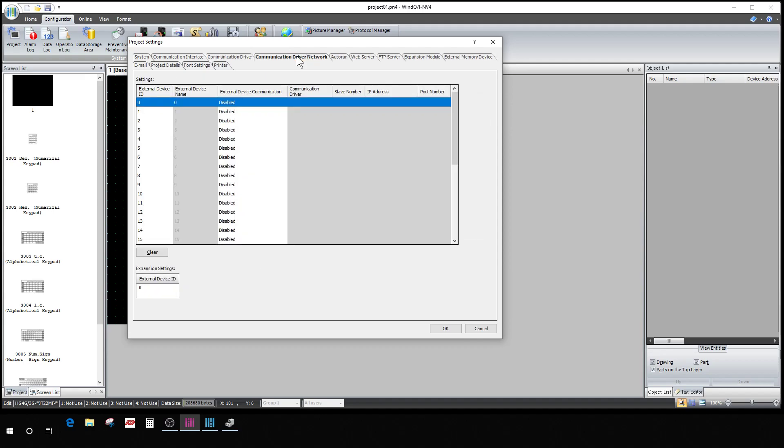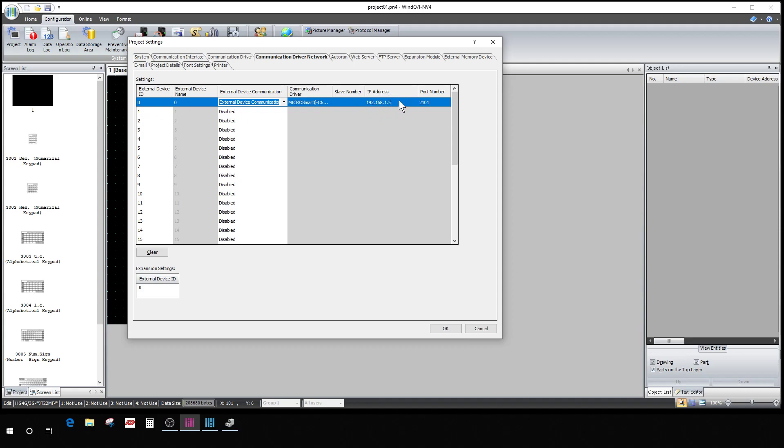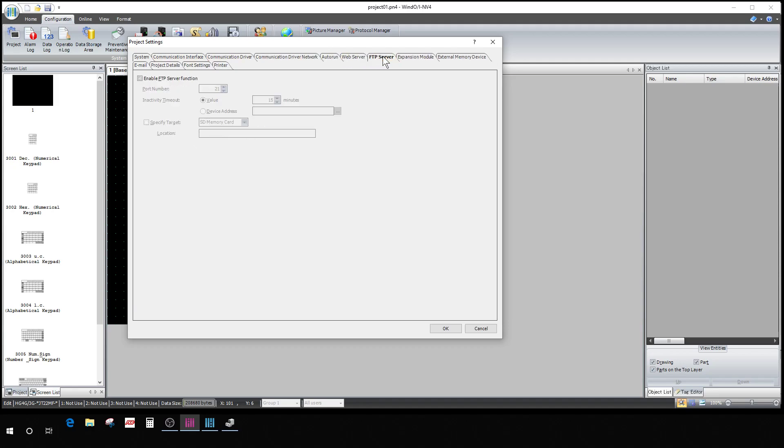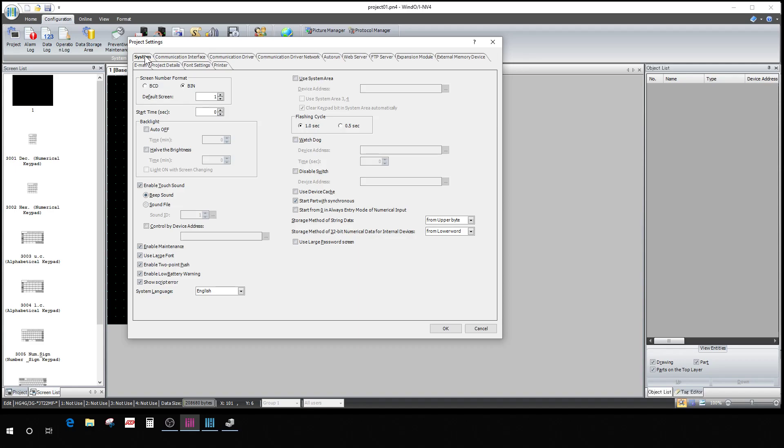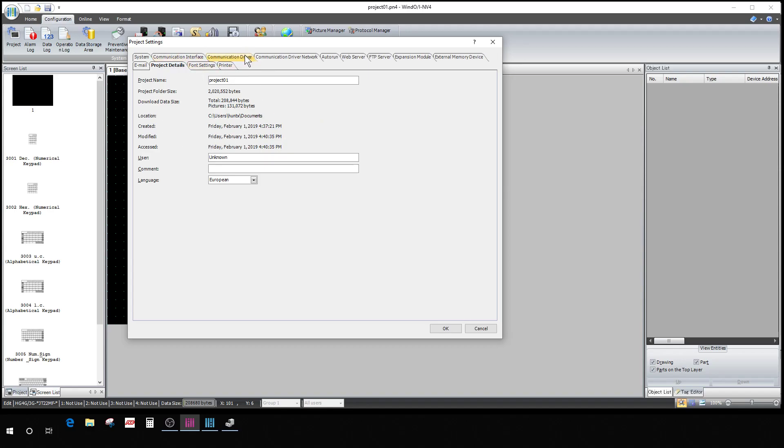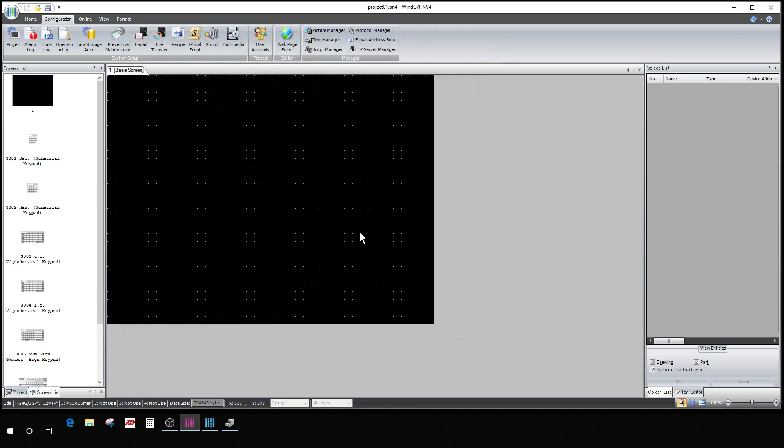Communication driver, network. You have to come into here now, external device communication 1. See I've changed that right there. It populates, this is what this HMI is communicating with: 192.168.1.5, which is your default IP address for your PLC. There's all kinds of other stuff you can do in here if you want to play around with some of it, but this is actually how you set up the whole thing for your whole HMI.